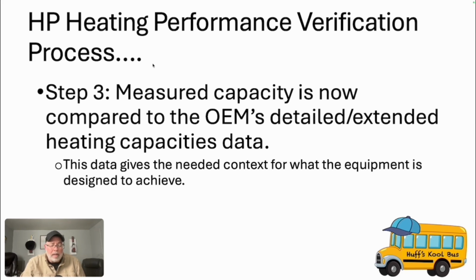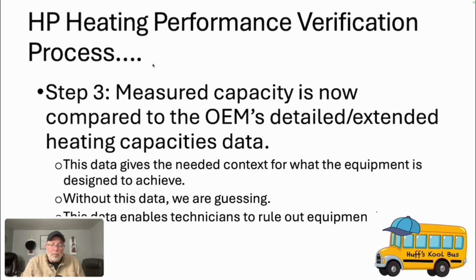So the only way to truly verify the performance is to take the measured capacity and compare it to what the manufacturer says it should be able to do. Without this data, we are just simply guessing. We're simply guessing. With this data, we're actually able to rule out any type of equipment issues, or we will uncover an equipment issue.